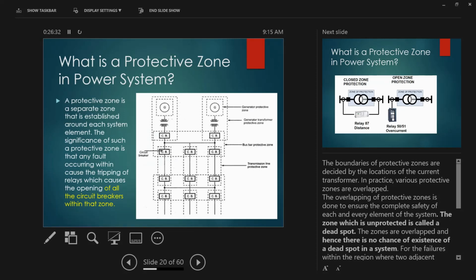There's no dead zone. There's some overlapping of protections for them to cover in case there is some kind of problem, or sometimes they do some redundancy of protection. Like for this one, this breaker is capable of tripping through a signal from bus differential if there is a bus short or fault. It's also capable of tripping through overcurrent on this zone. So you see the overlapping over there. That's why setting is very important. Any question?